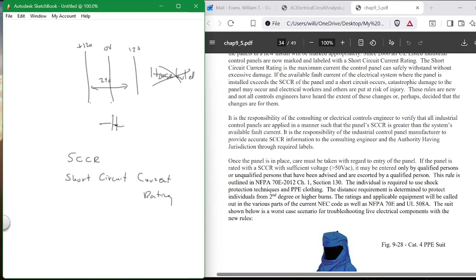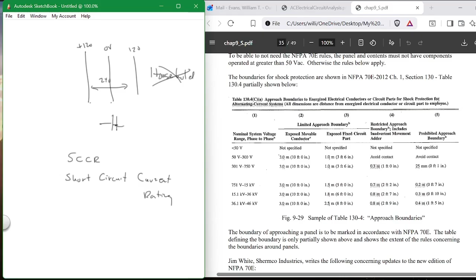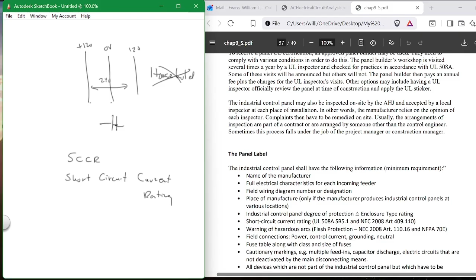But if you open that panel, you might end up needing to wear a suit like this, the worst case. There are four levels of severity, and this is level 4. Why would you need to wear something like this? If there's an explosion in the panel, you can get killed. It's not electrocution, it's a spray of molten copper, and it will kill.